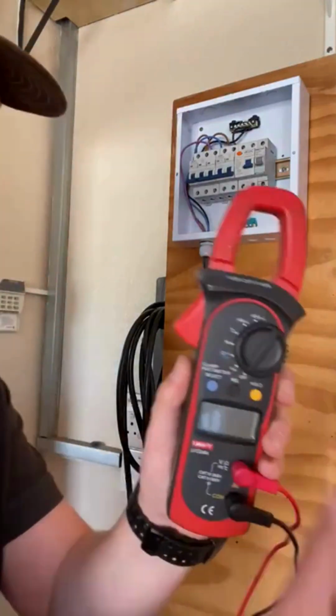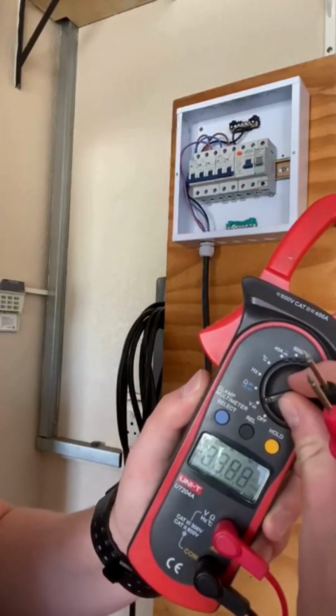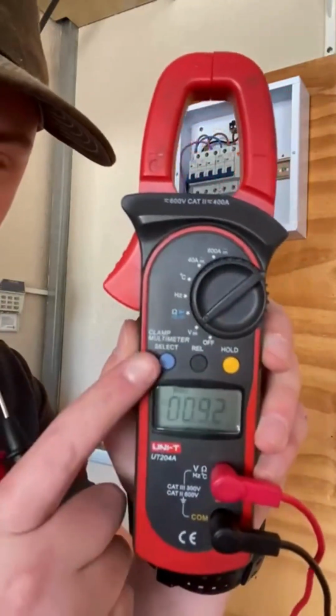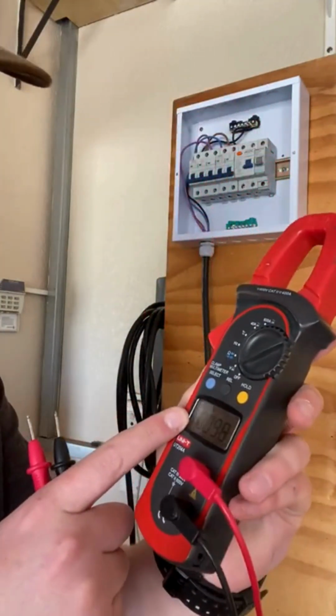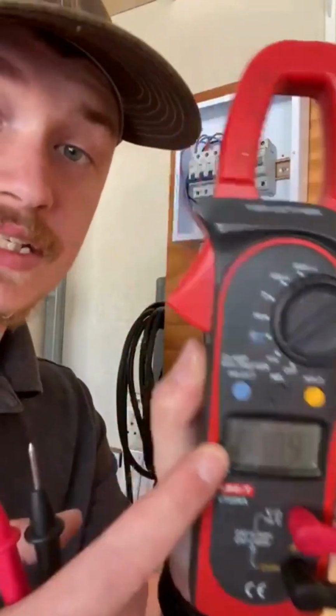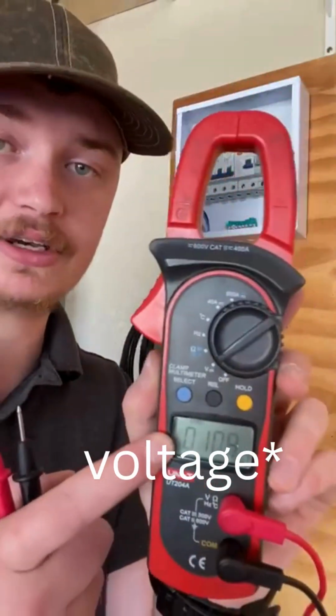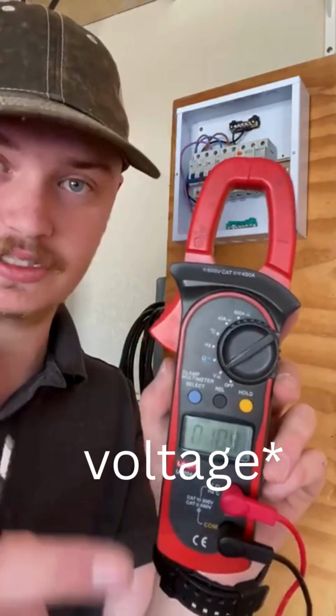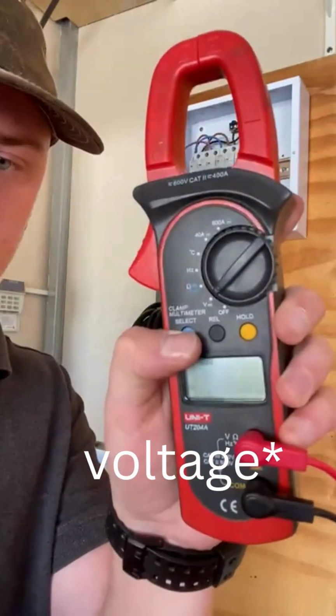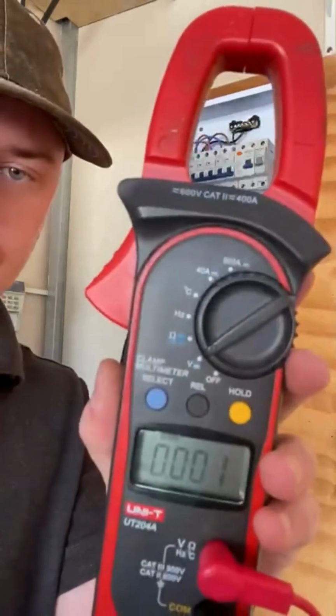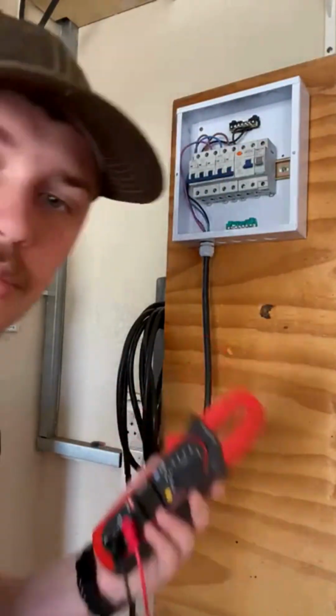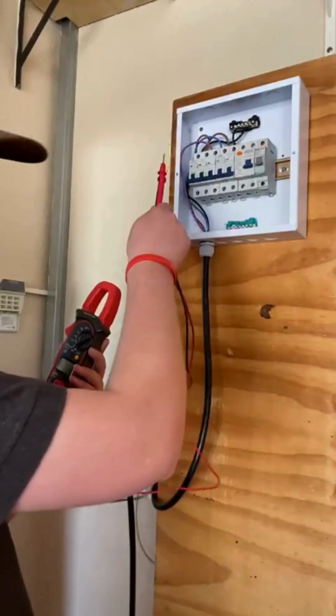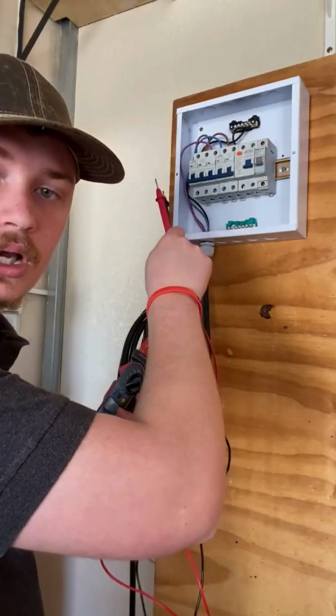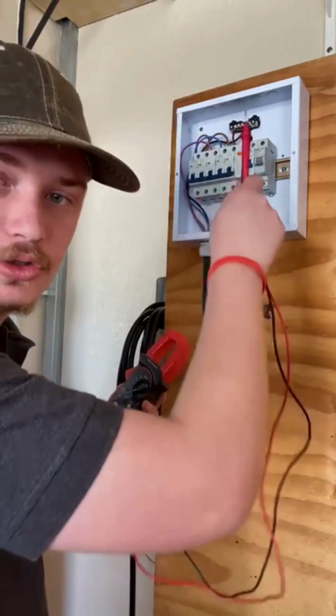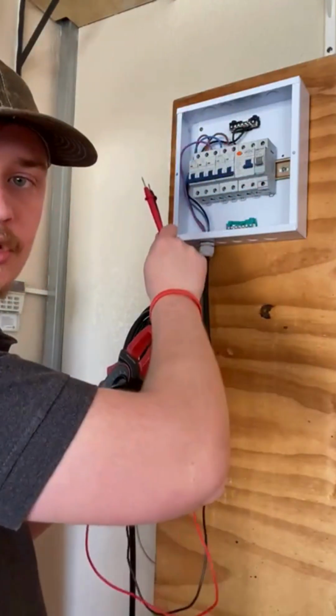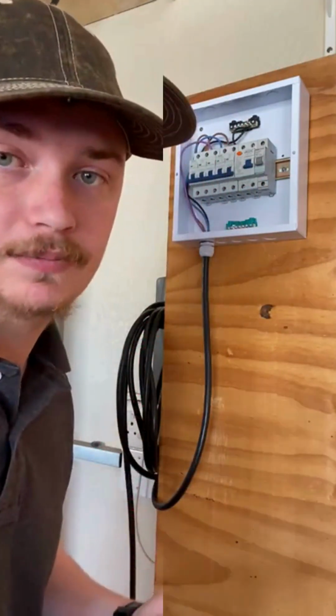So on my multimeter, we turn it to voltage. You can see here it indicates DC, but we're not measuring DC, we're measuring AC voltage at this moment. So we select AC. We're going to measure from L1 to neutral, L2 to neutral, L3 to neutral, and then between phases as well.